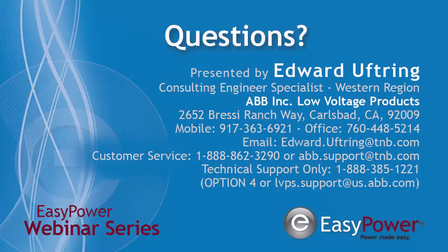Can you explain what you mean by electronic trip unit? An electronic trip unit is a trip unit that sits onto the device. We have dip switches that allow you to set the LSI, but also you can plug into the electronic trip unit through an Ekip software program that allows you to set all these parameters up with your computer and move on.